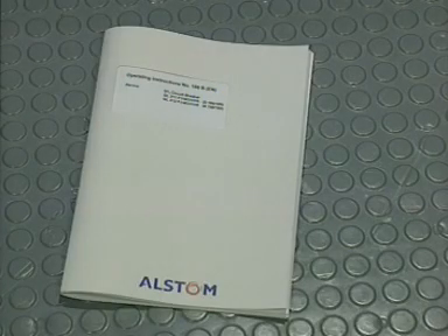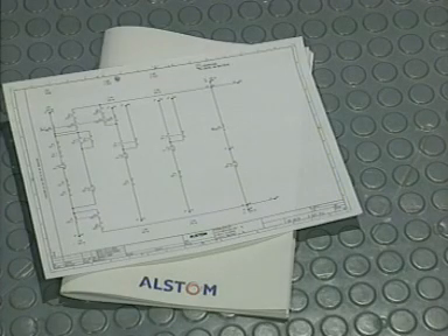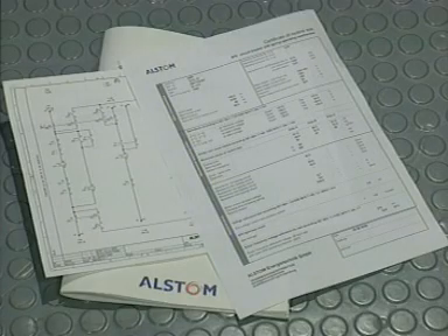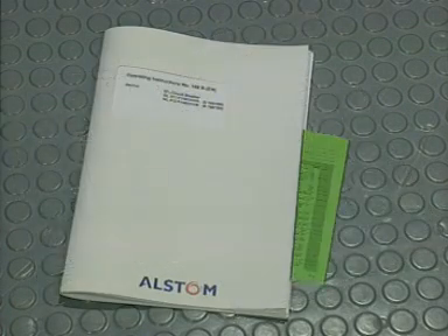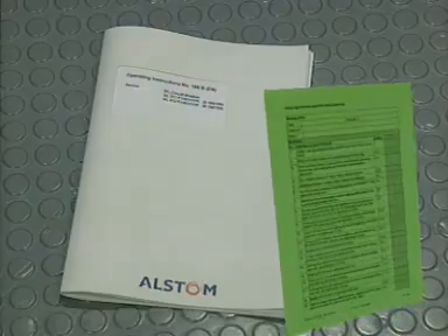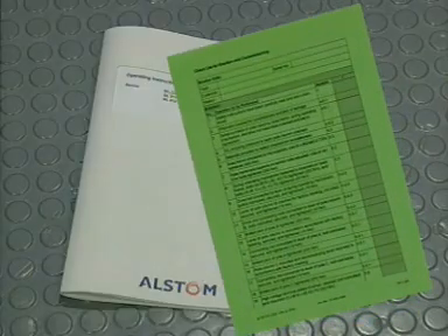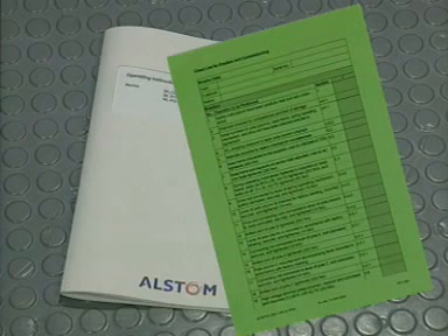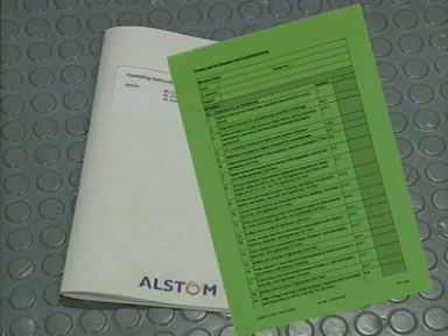The following items are required for reconditioning purposes: operating manual, schematic diagram and routine testing certificate. A checklist can be found in the operating manual and must be filled out during the entire repair process. This ensures that all the important procedures that guarantee breaker operating safety and reliability will be carried out and documented.